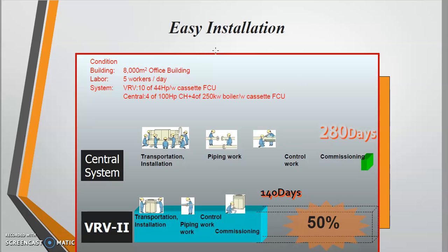Compared to the VRV system, of course, they still need the transportation and installation process for the outdoor unit and then the indoor unit. And then the piping work is much easier to handle compared to the piping work of the centralized system, because in the centralized system they are installing piping for the chilled water system. But for the piping work of VRV system, it is just a copper pipe, and they have ready stock of branches when we want to branch the pipe multiple times, and then some control work, and then the commissioning work. It is believed that when we install the VRV system, it can cut installation days by 50%, which took about 140 days only, compared to the centralized system, which took about 280 days.